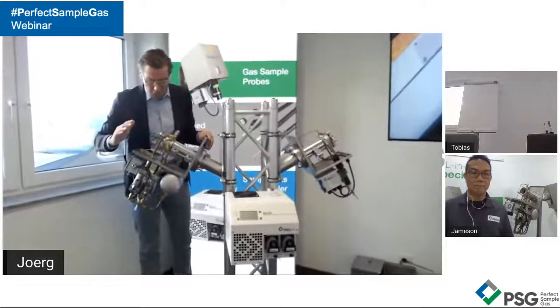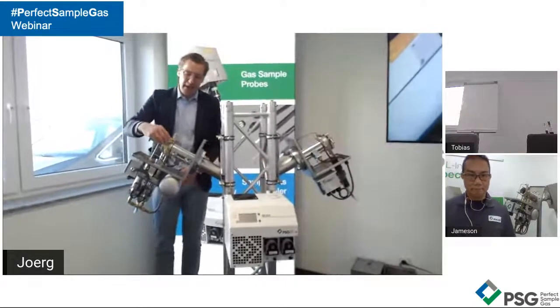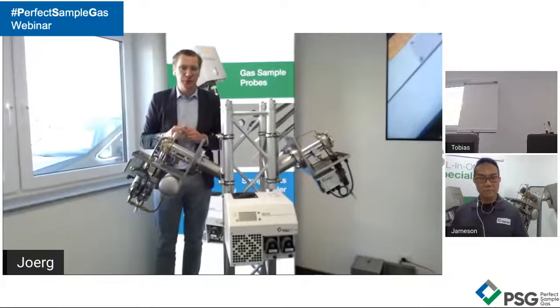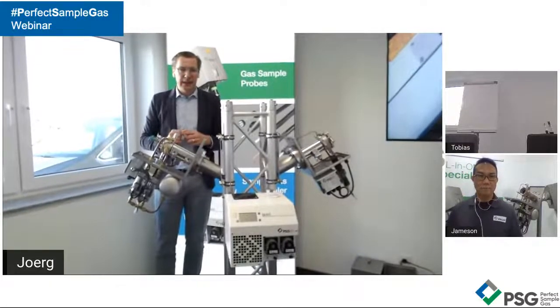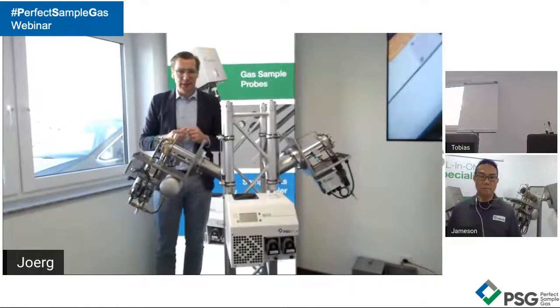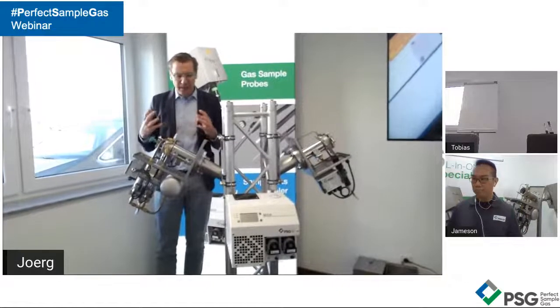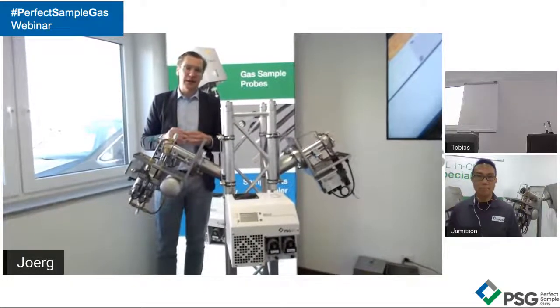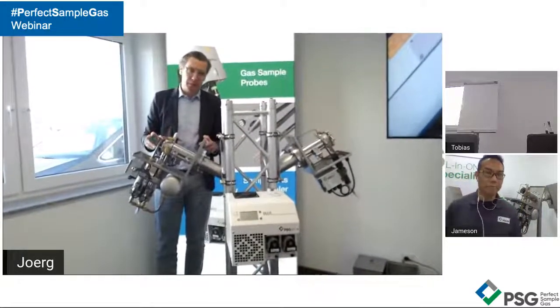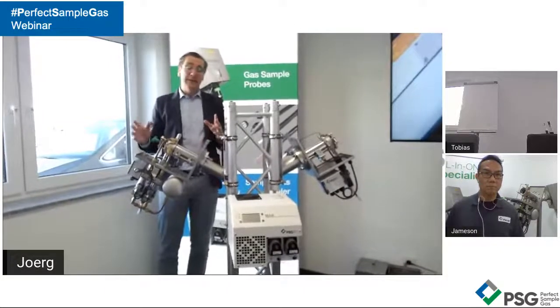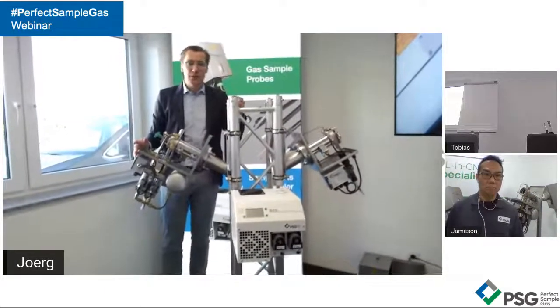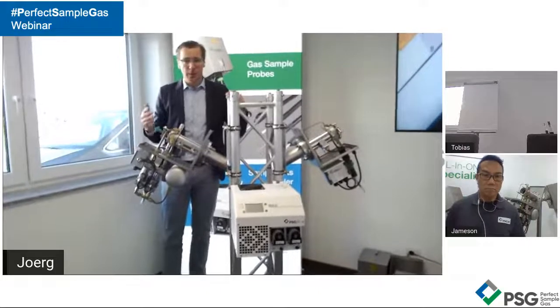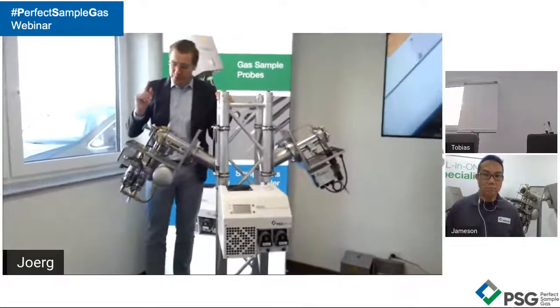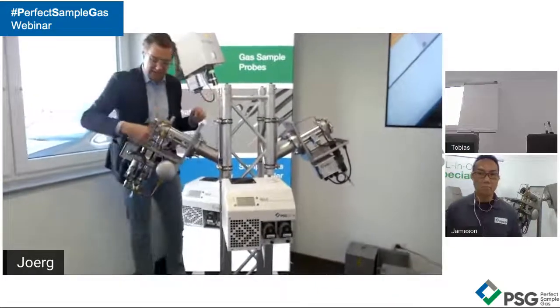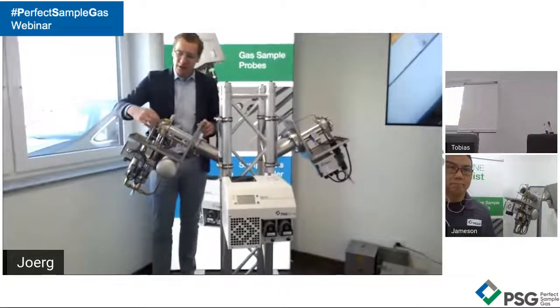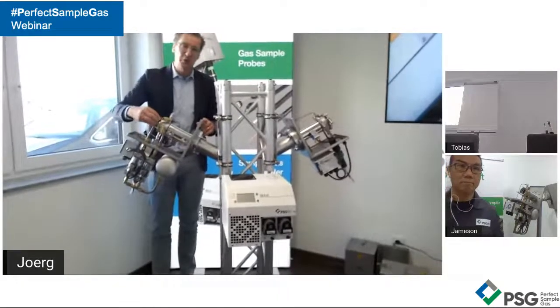First of all, one of the very important things is we have to make the purging of the instrument as efficient as possible. You might find other products in the market with a back purging, even probe solutions with a dual stage or double back purging, but what you're not going to find is this unique dimension of the tubing.